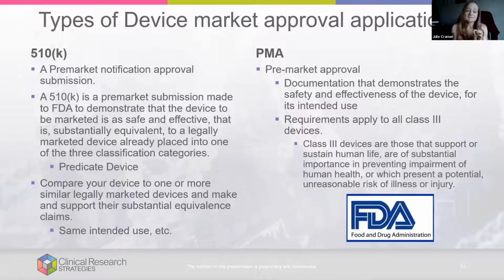The reason is that if the predicate device has the same safety and effectiveness as your device, or if your device has the same safety and effectiveness as the predicate device, then you have a less steep clinical evidence barrier to get over than if you didn't have a predicate device, because someone has already done those studies in the predicate device. As long as you can say, my device meets those standards, what has already been done for that predicate device. So what you're doing in the 510K is just that.